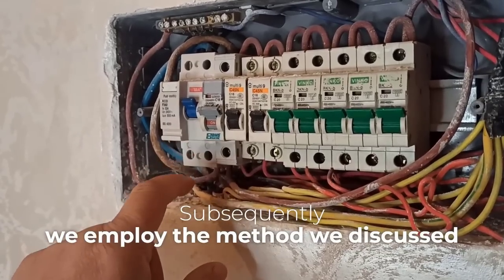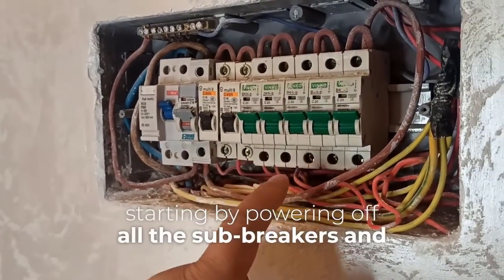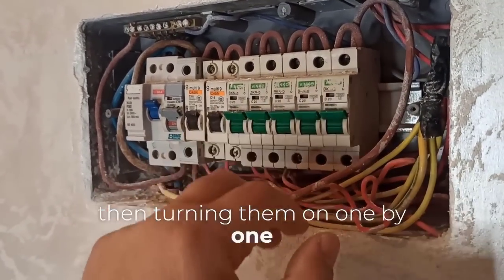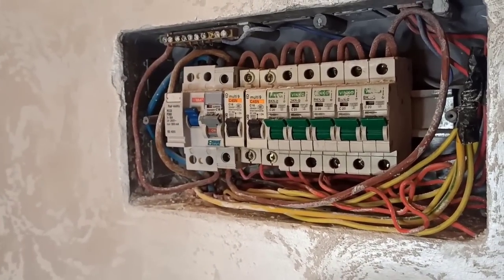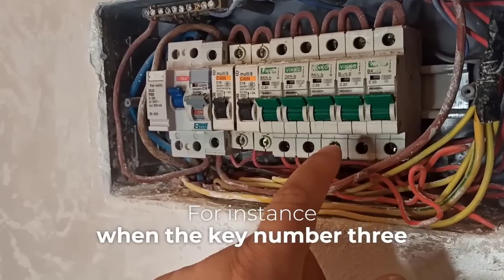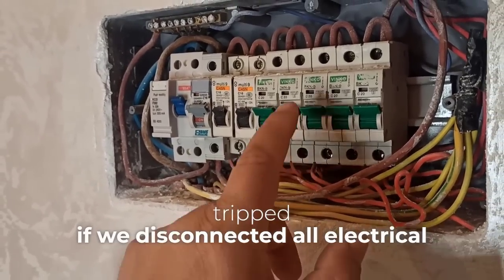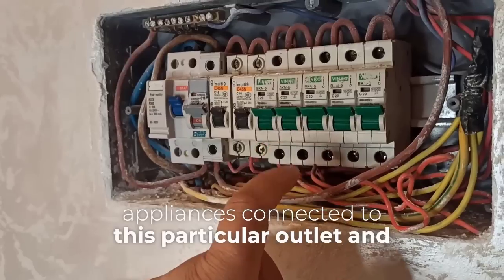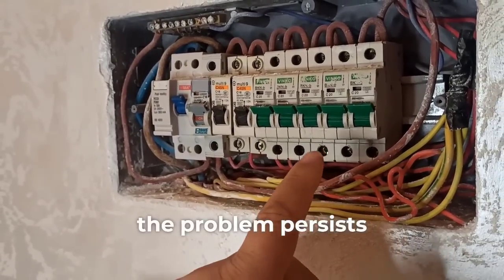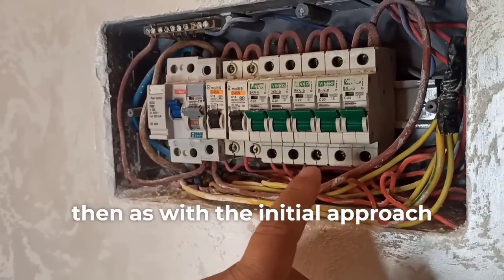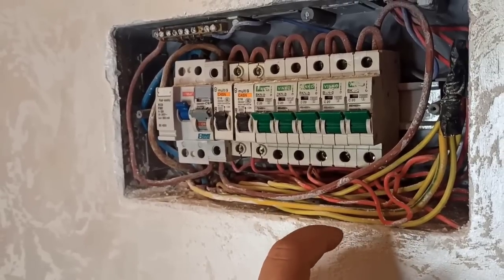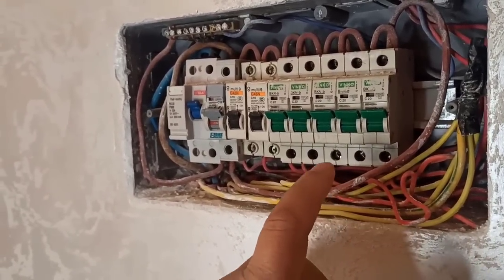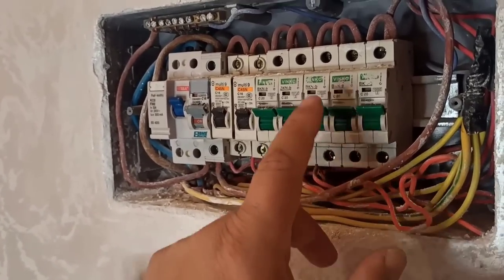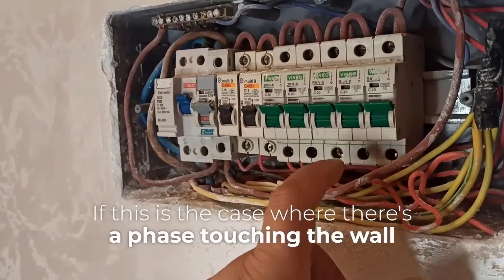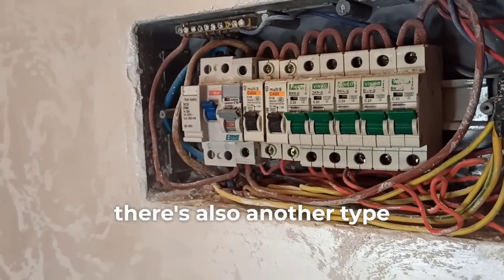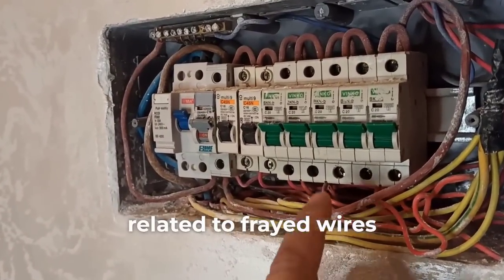Subsequently, we employ the method we discussed, starting by powering off all the sub-breakers and then turning them on one by one. For instance, when breaker number 3 tripped, if we disconnected all electrical appliances connected to this particular outlet and the problem persists, then, as with the initial approach, we still have the issue. If this is the case where there's a phase touching the wall, there's also another type, related to frayed wires.